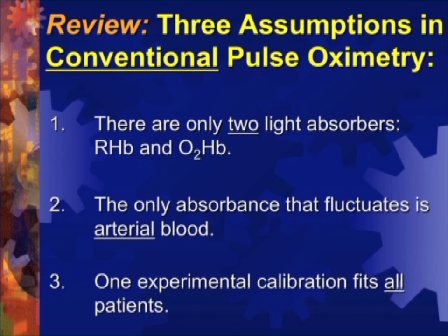Knowing those 3 assumptions and keeping them in mind, this is why I tell the clinicians, you can predict when the pulse oximeter is likely to be giving you inaccurate values. One category of errors is low signal to noise ratio. Light interference is one of the causes of that. In early pulse oximeters, that was a serious problem. It's less of a problem now, but it's always a good idea not to have bright room lights shining directly on the pulse oximeter probe. Cover it up, shield it.